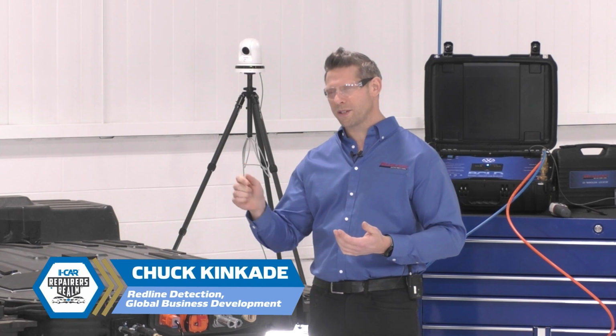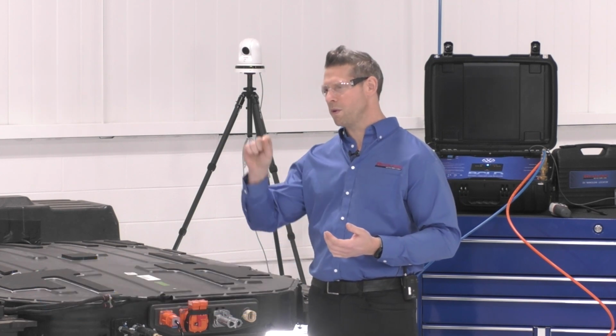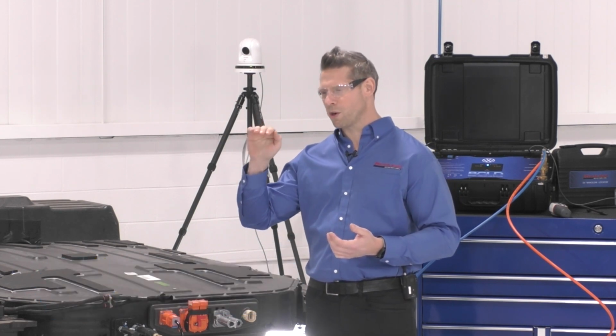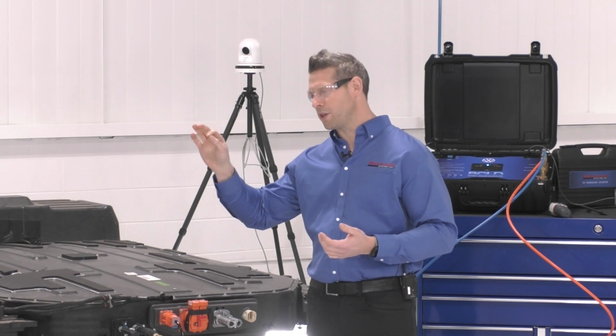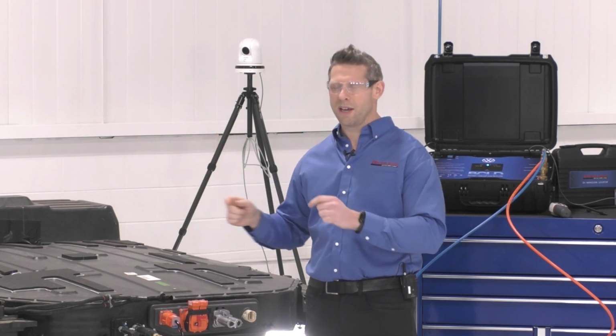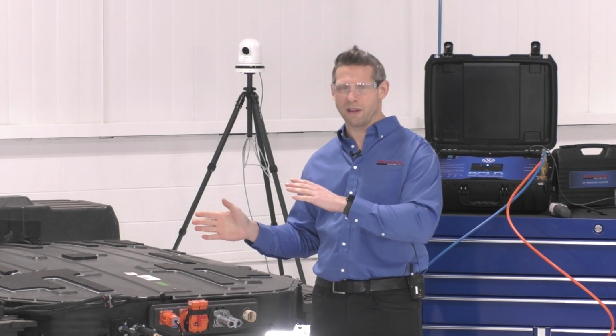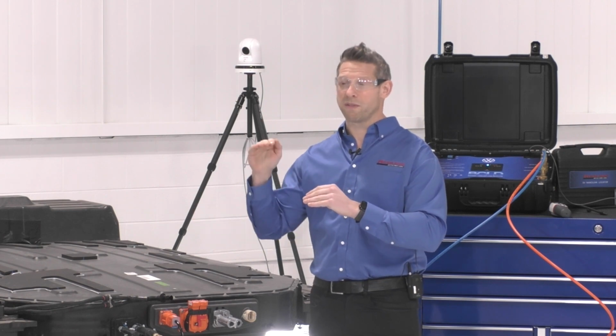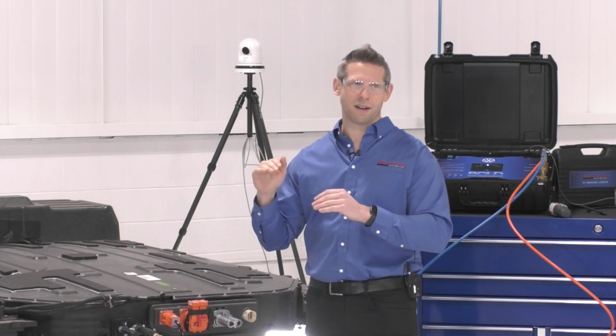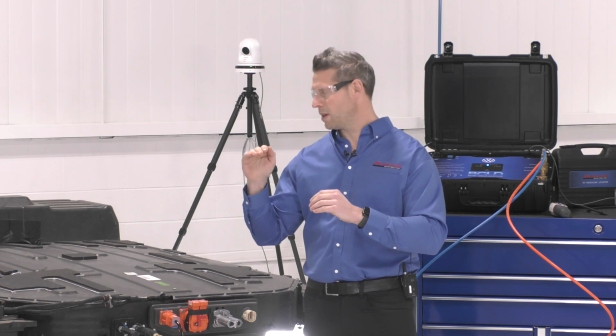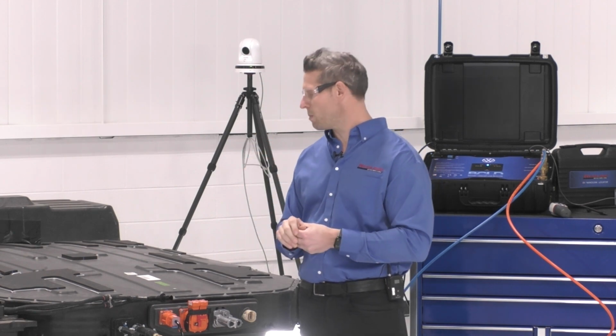I would say the second most often would be a vacuum rise test. These are tests where you pump to a certain enclosure pressure, you let that pressure stabilize, and then you watch the decay over time. And from there, you can understand what the leak rate of that battery is. There's a specification you need to meet of whether that battery meets that leak rate specification or not. So that's a pass or fail.